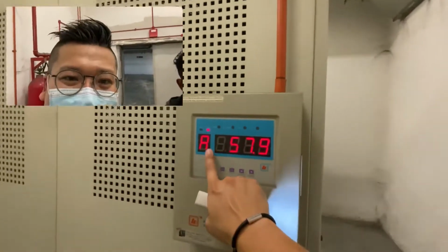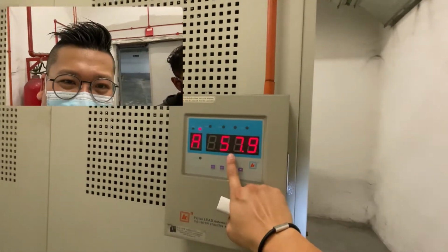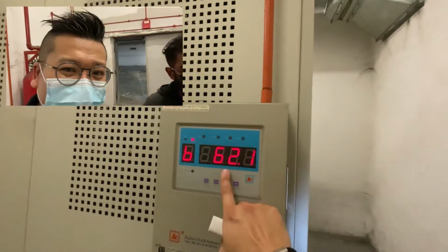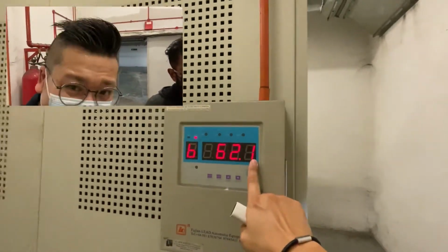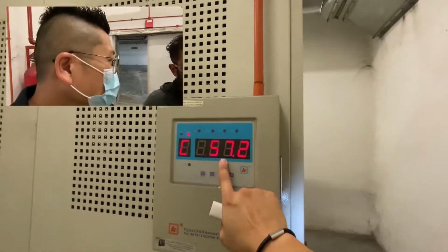Referring to P. A is red phase, B is yellow phase, 62.1 is the highest. C is a bit low because it's at the side. So we take the center core temperature as reference.